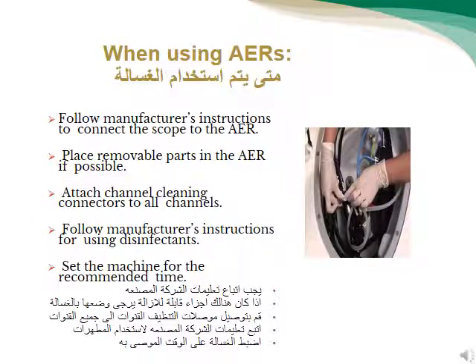When using an automated endoscope reprocessor: follow manufacturer instructions to connect the scope to the AER, place removable parts in the AER if possible, attach channel cleaning connectors to all channels, follow manufacturer's instructions for using disinfectants, and set the machine for the recommended time.